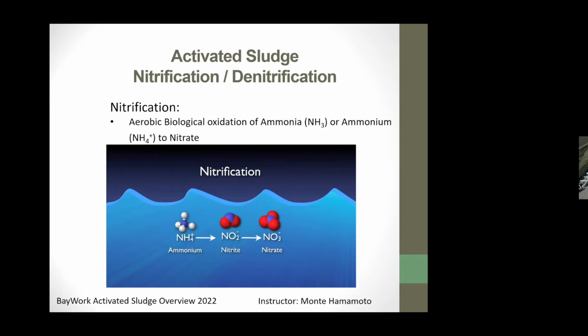When we have a drought here at Silicon Valley Clean Water, everybody's conserving water. We'll notice our average flow is around 14 MGD, and during drought conditions, with water conservation happening, we're down about 11 MGD, but guess what? The strength of the wastewater hasn't changed. Still the same amount of solids, still the same amount of ammonia. But when you take the water away from it, what happens? The concentration goes up. Ours has gotten as high as 70 parts per million. So it's a big concern of ours, and that's why we're really focusing on what we're going to do, and we're kind of being proactive and trying to move early on some type of a way to reduce the amount of ammonia we have in our wastewater stream and treat it.